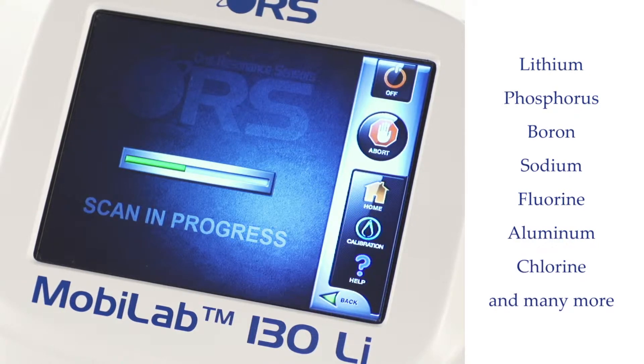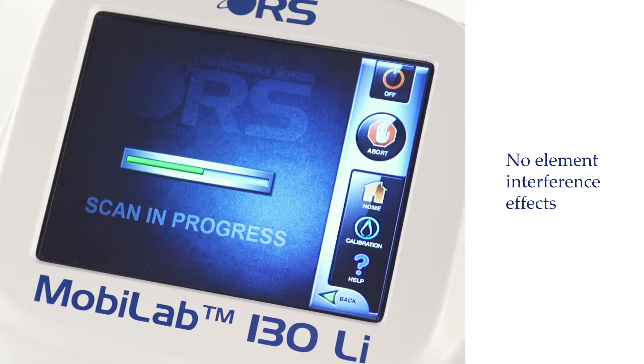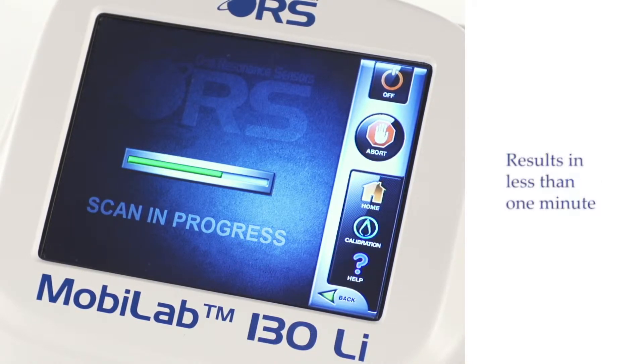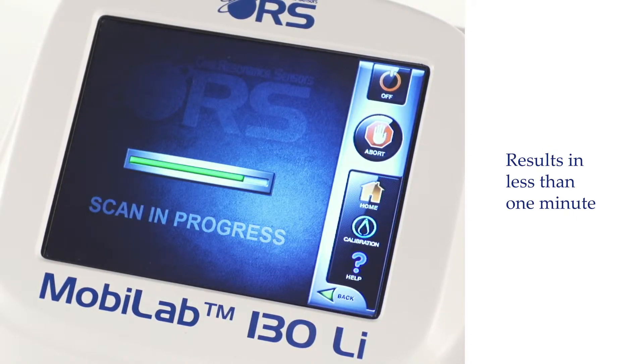The MobiLab 130 offers the flexibility to analyze a large number of elements without any element interference effects, a common issue for standard analytical methods. The device measures the number of atoms per unit of volume, from parts per million to limit of saturation.